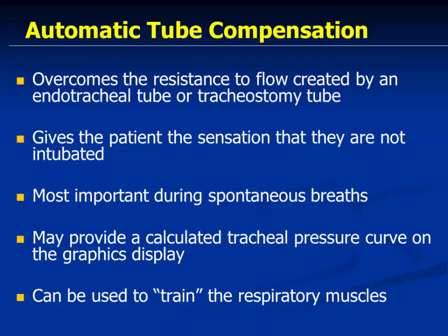And mind you, we are measuring pressures at what level? We are not measuring airway pressures or PEEP at the tracheal or carinal level. We are measuring those pressures outside the tube, most of the time either at the expiratory port or with the transducer at the Y connector. In a few ventilators you connect the transducer there. So we are not measuring the exact pressure changes happening at the carina because of the endotracheal tube.